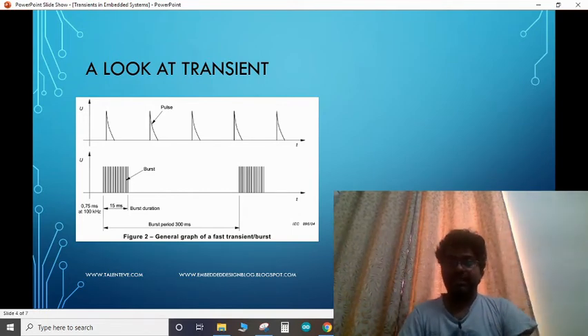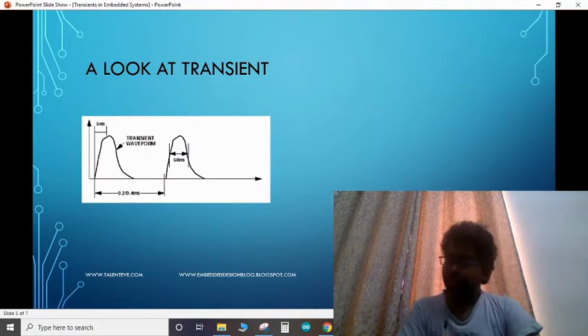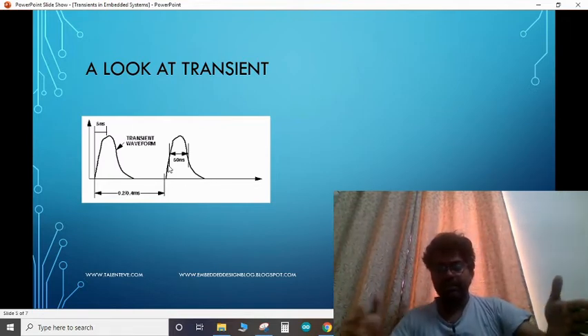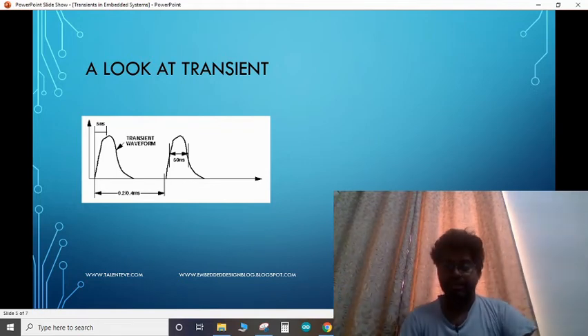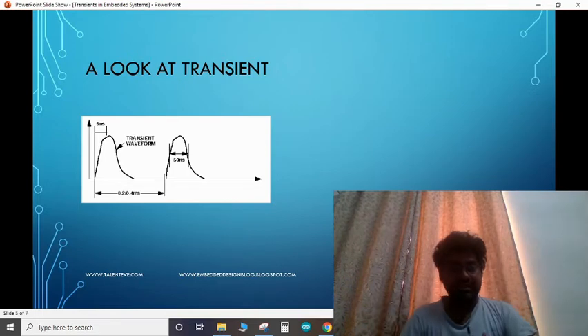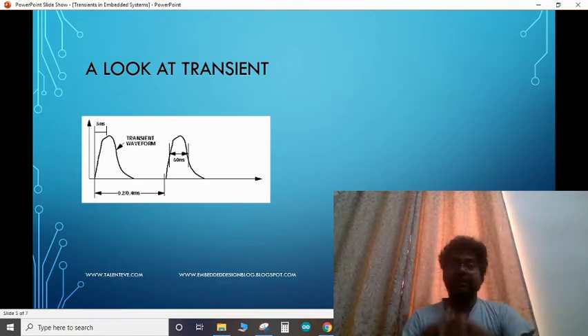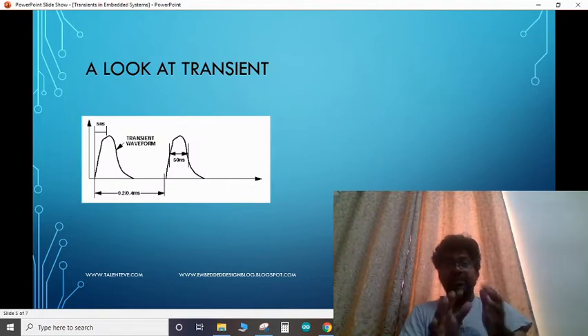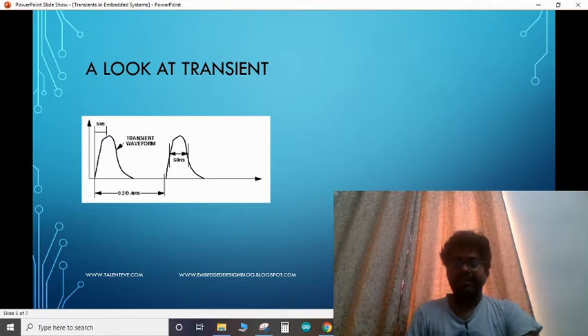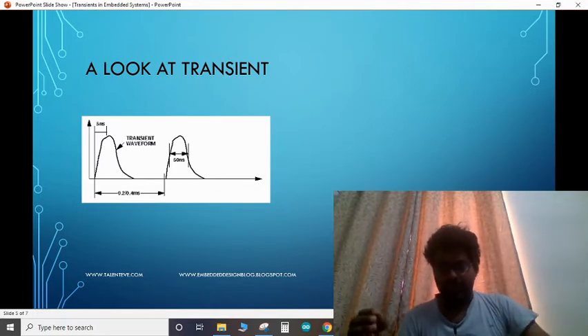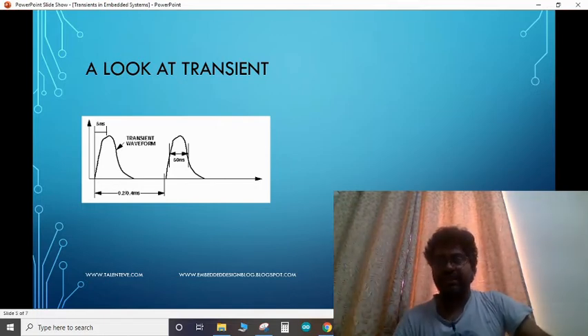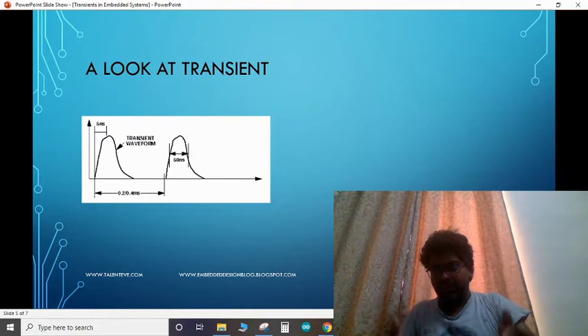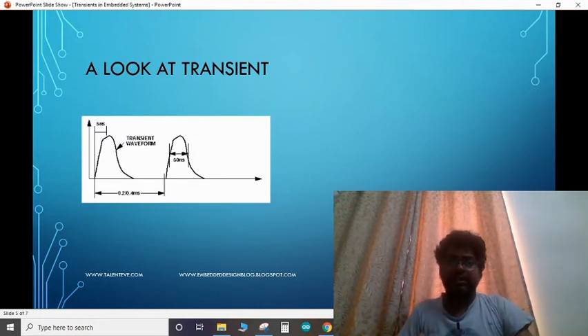This is how we test a device, and it is part of the IEC standard. Taking a closer look at the transient waveform, a bunch of these waveforms applied together is called a burst. The transient voltage can go up to 2 kV in some cases. Lightning produces a very fast transient, whereas switching of high loads on the board produces a slower transient that can have a duration in milliseconds. The transient characteristics vary based on the source of generation.